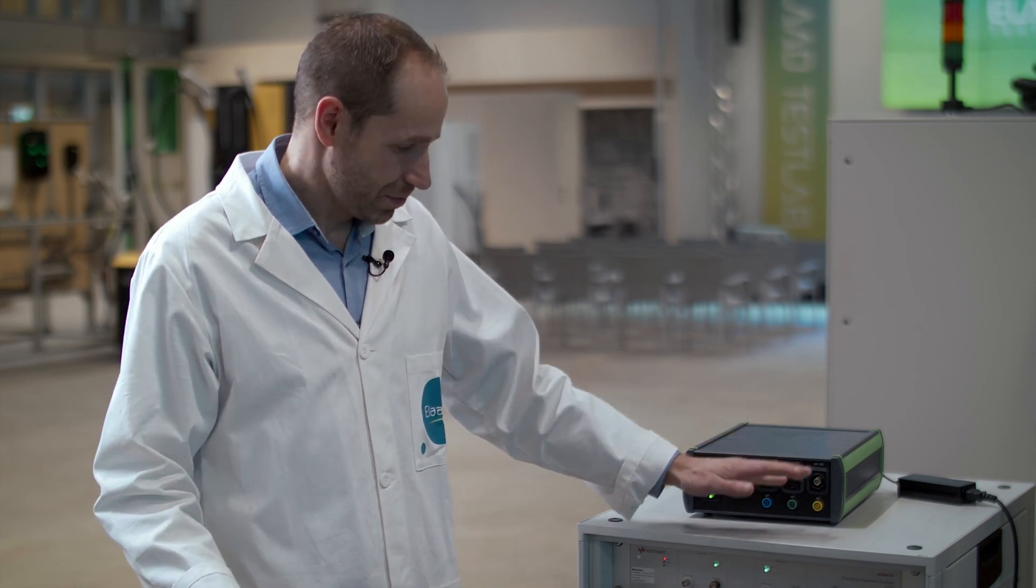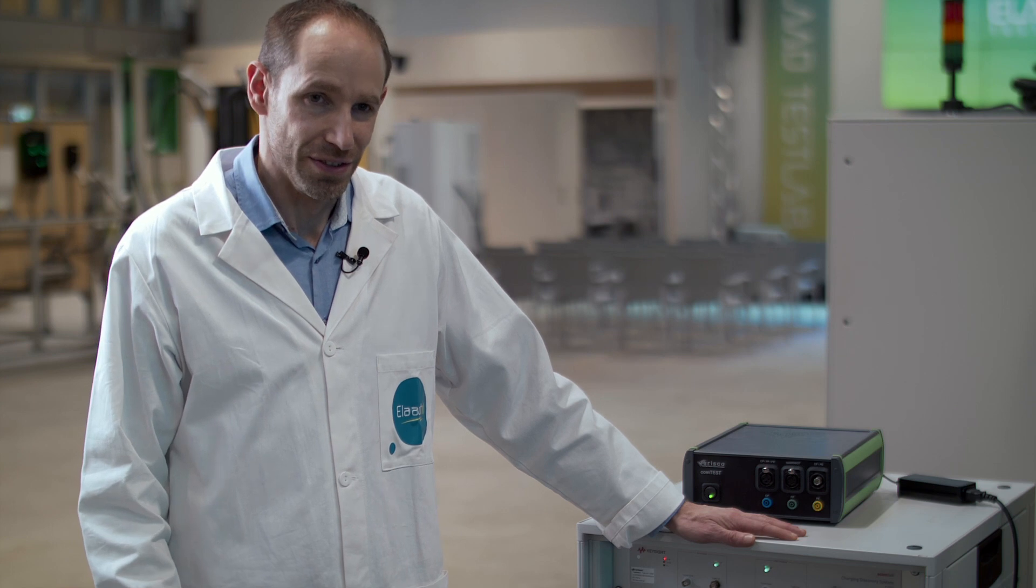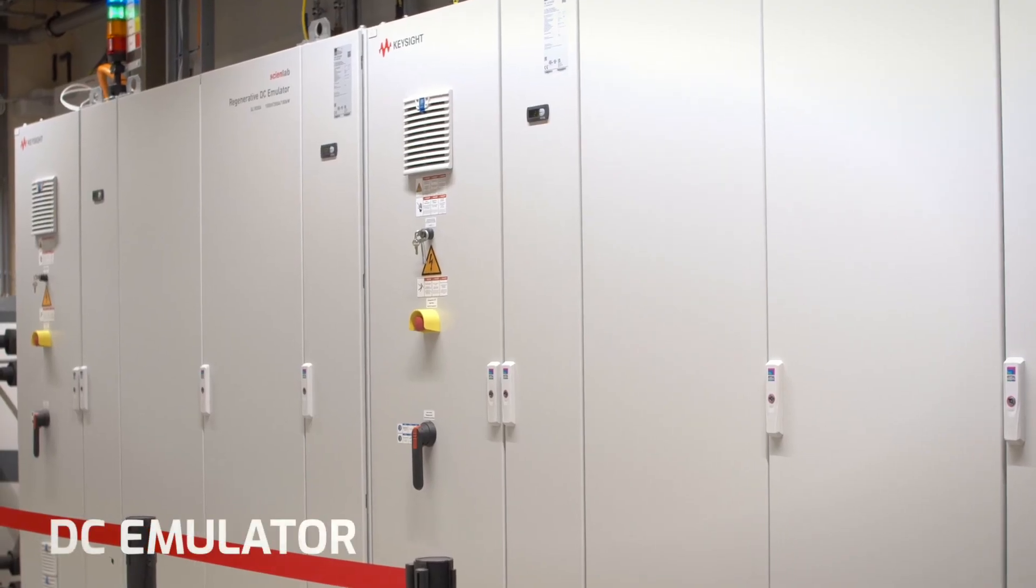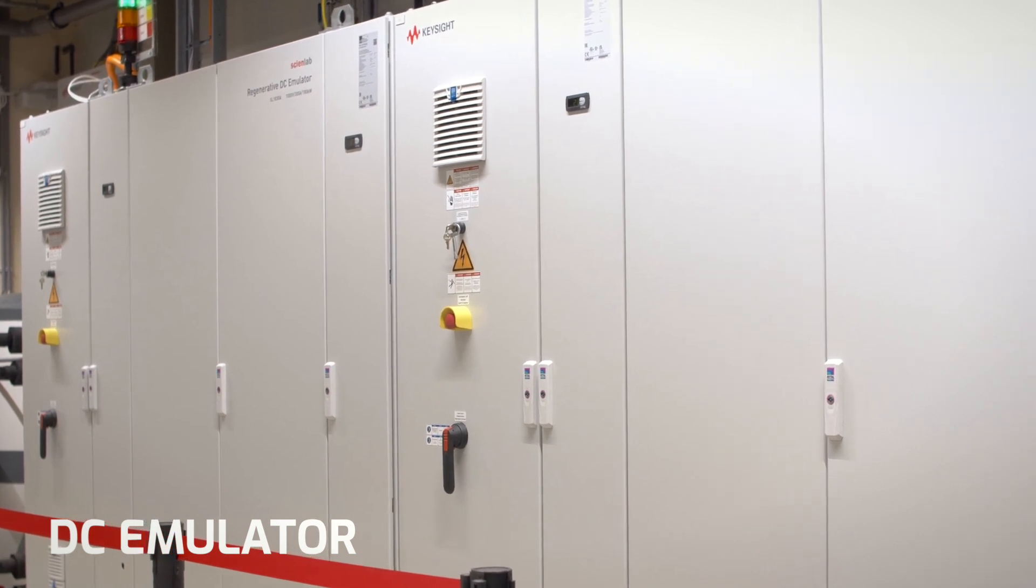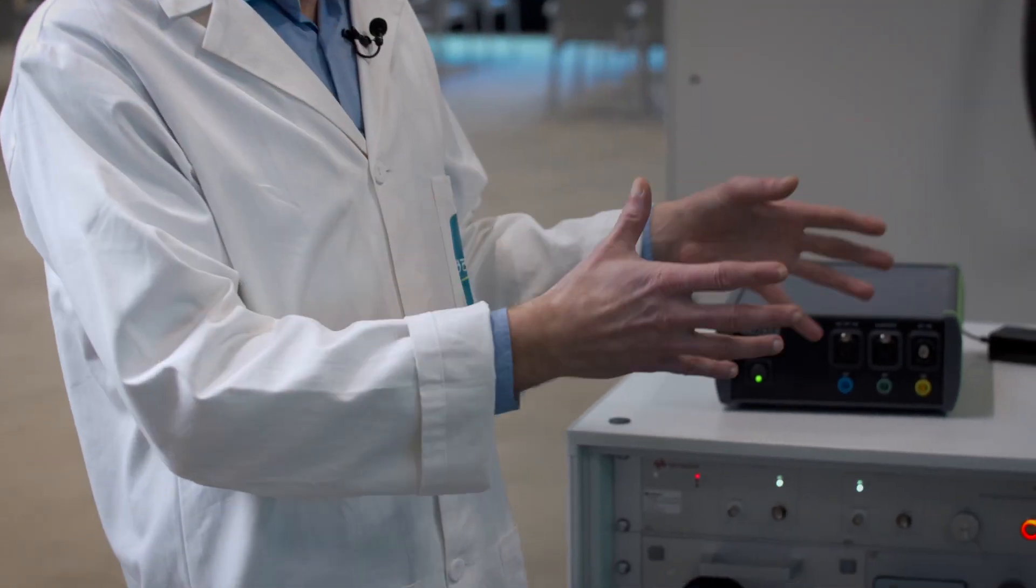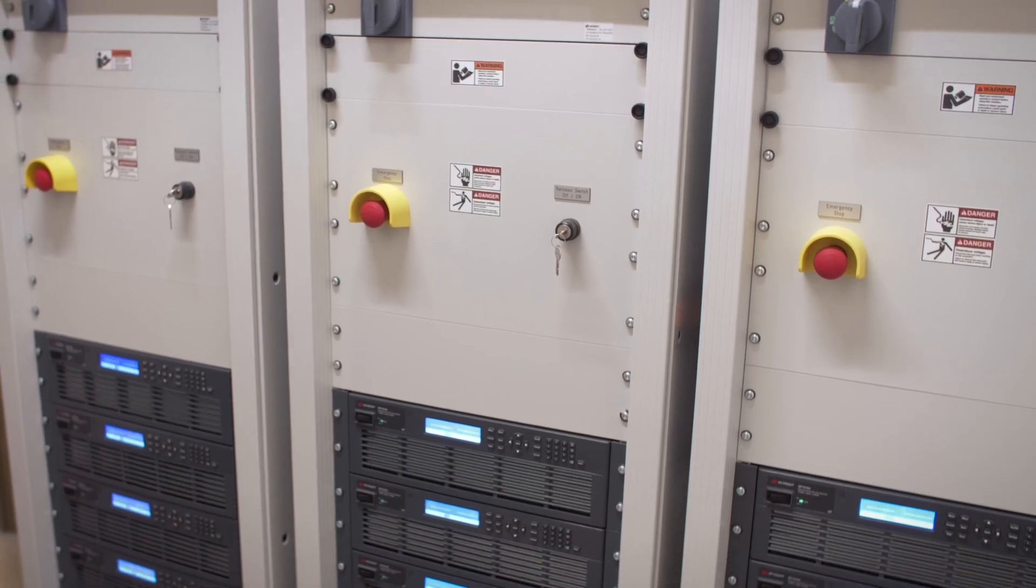So the other thing we can test with the system are the DC chargers. When we do these tests, we take this one again, and we make this pretend to be an electric vehicle that wants to charge on DC. Then we connect this one to the DC supplies we have. And these DC supplies, they emulate the battery of the electric vehicle, and the charging station itself, we connect that to the AC grid emulators we have.